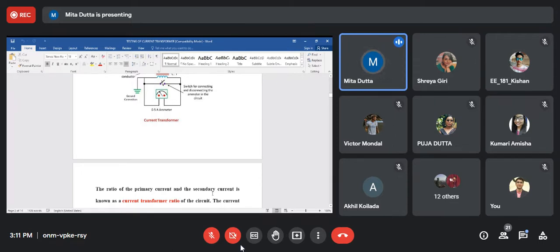And rated means the current that the transformer primary winding is able to carry without excessive temperature rise. The nominal ratio should be written on the nameplate of a current transformer. Since the transformer is not ideal, the nominal ratio written on the nameplate will differ from the current transformation ratio, which is the current flowing through the primary winding divided by the current flowing through the secondary winding.